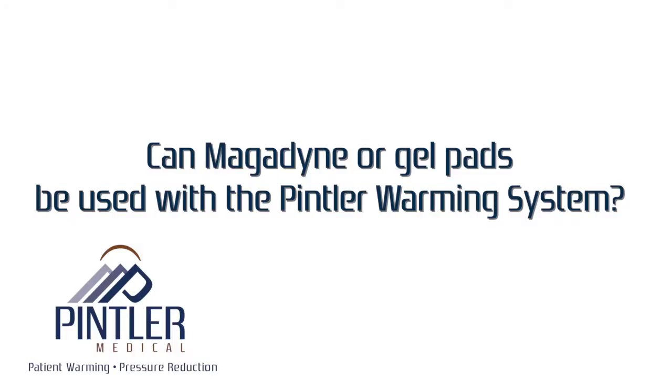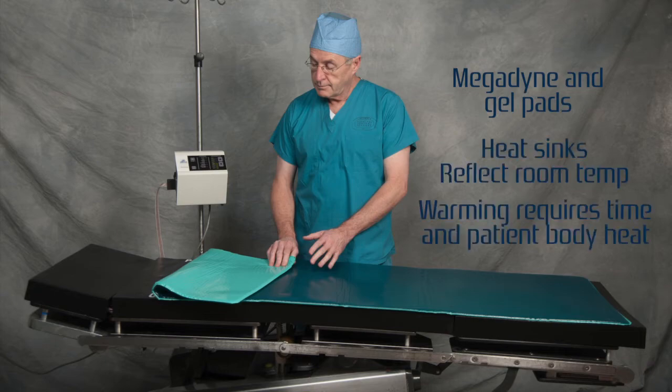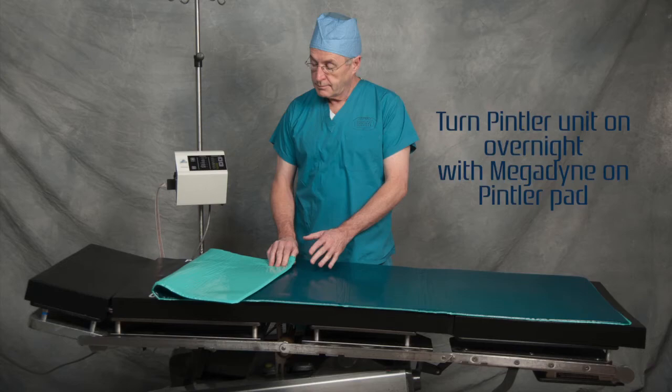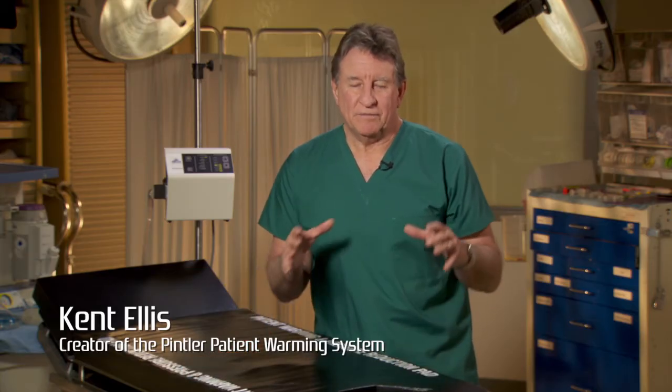Can a Megadyne or gel pad be used with the Pintler warming system? Megadyne with a gel face and gel pads are both heat sinks — they reflect the room temperature. Warming the gel requires time and the patient's own body heat, making it an obstruction to achieving patient normothermia. If the Megadyne is required, it is suggested that the Pintler unit be turned on overnight with the Megadyne pad placed on the Pintler pad. Alternatively, the Megadyne gel pad can be placed on the lower third of the torso pad. Check with your Megadyne rep before using the two together, as Megadyne is an evolving technology.